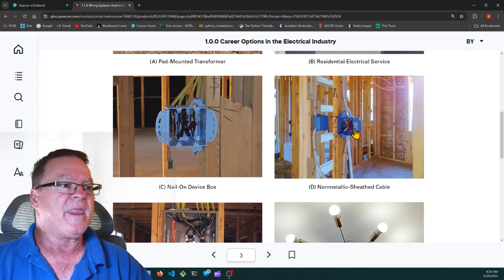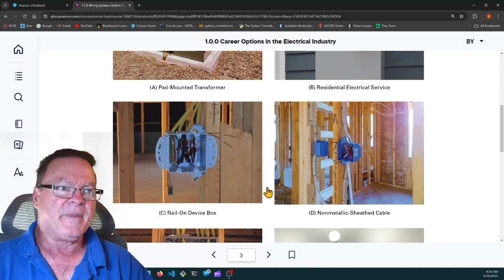And then an inspector comes. You can't just drywall over it—you won't be able to see what happened in the walls. They want to make sure that the Romex is stapled within 8 inches of every plastic box and every 4.5 feet. So you have to get a rough-in inspection. The inspector comes and sees it, says yeah, everything's up to code.